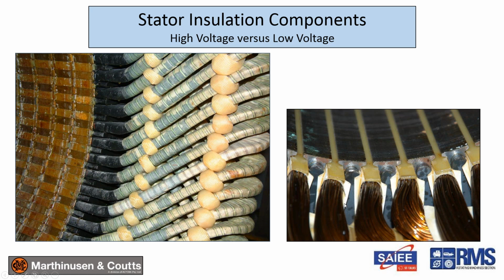Okay, and then the overhang of a low voltage machine is very similar. Your slot portion and your overhang portion. Obviously, you don't have any of the anti-corona stress grading components that you need in a high voltage machine.